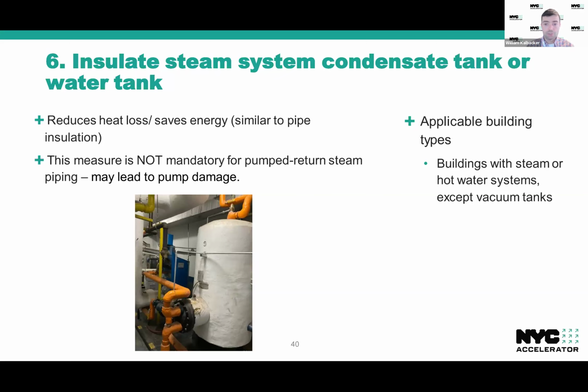This is going to be applicable to buildings with steam and hot water systems, with the exception of vacuum tanks. So if you're running a steam system on a vacuum and you have a vacuum tank, you do not need to insulate the vacuum tank. You also do not need to insulate a tank that's part of a pumped return system, because if you are pumping a very hot fluid, which the insulation will hopefully keep hot, you might incur some pump damage. So it's not required in those situations either.